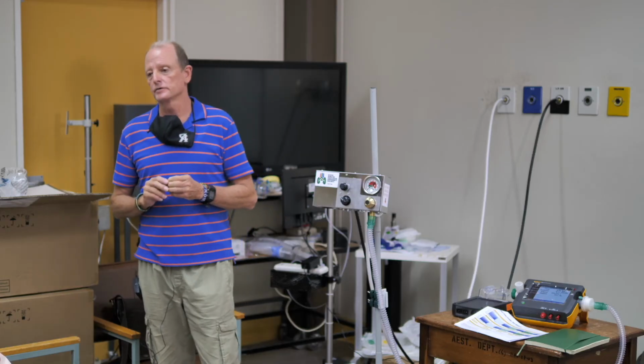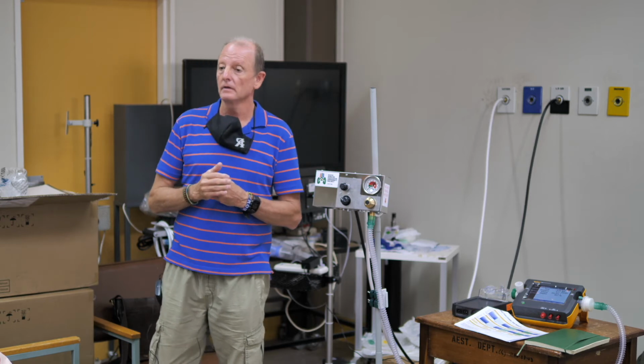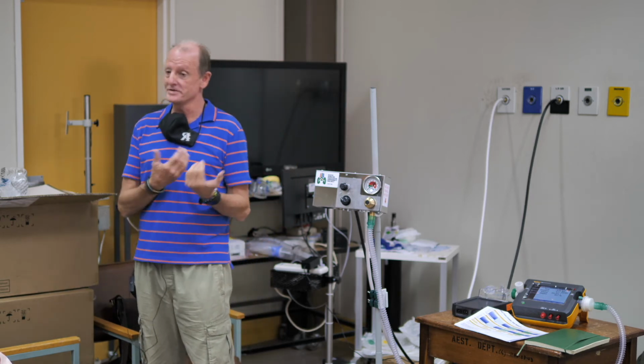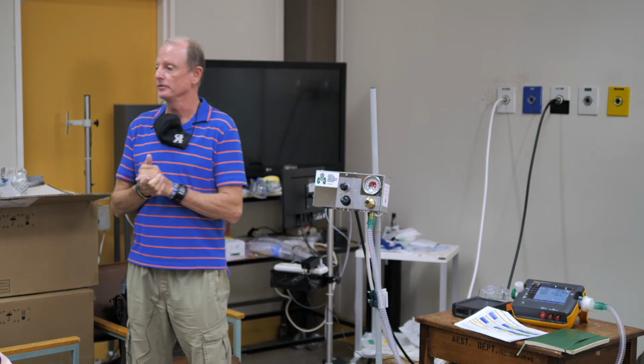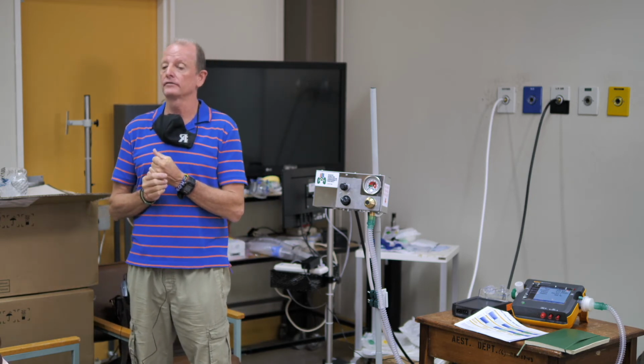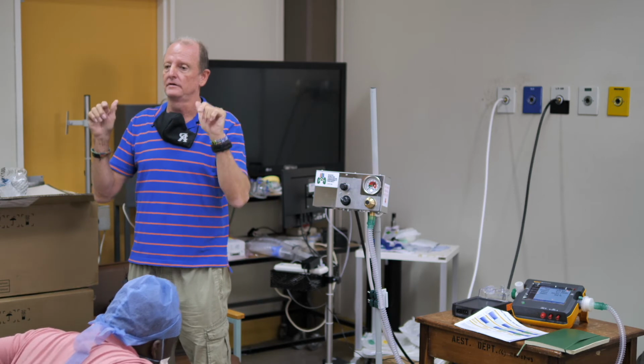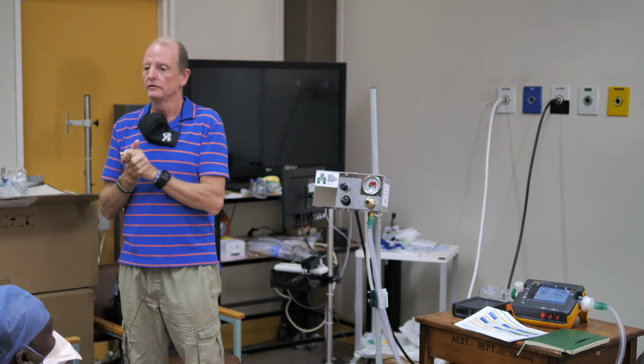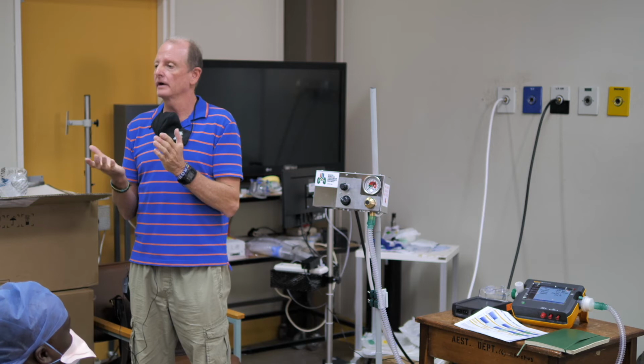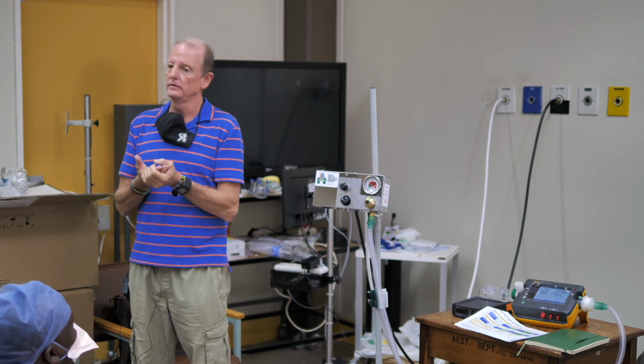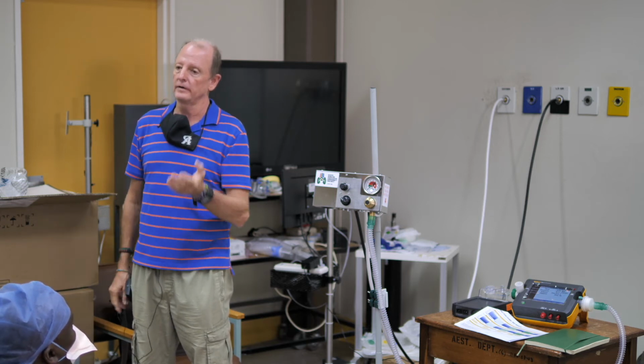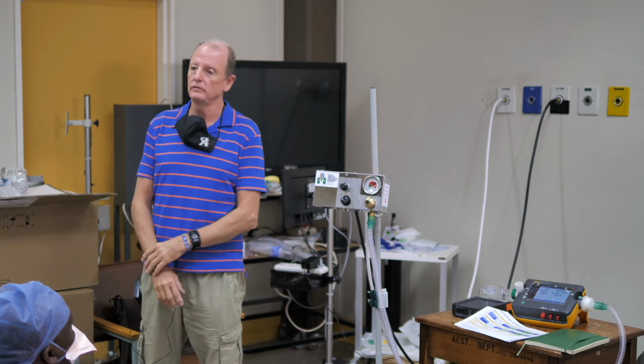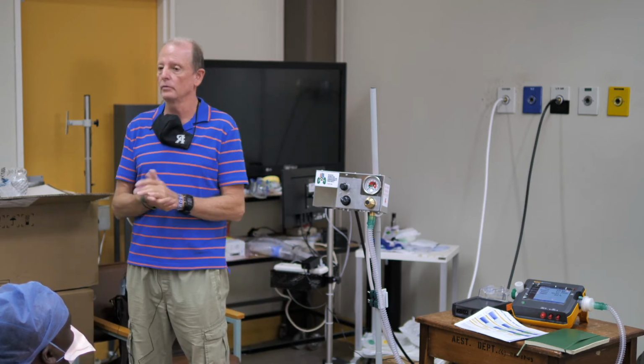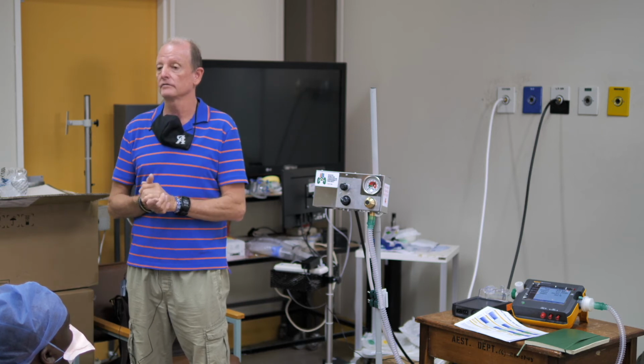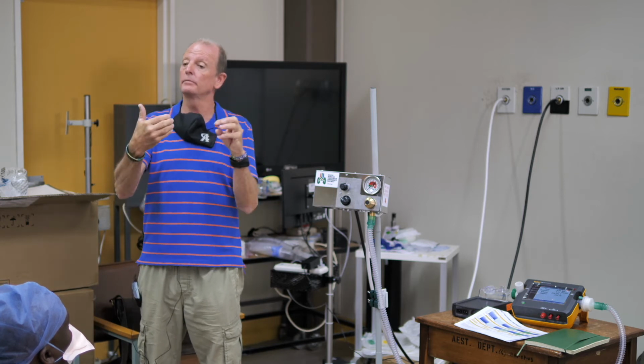No, unfortunately not. I mean, it can be readjusted again. It's simple to do, to bring it into line. So if someone requires it only for peds or something like that, down to about 3 liters a minute, but there again, if you want something that low, you're going to use a flow meter blender. You're going to use a flow meter plugged straight into a wall from 0 to 5 liters. And you'll probably have a flow meter connected to a blender anyway.